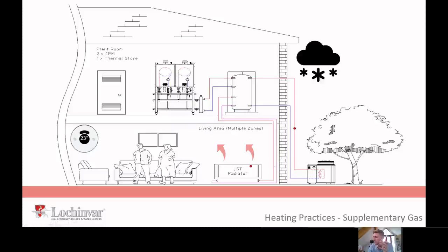So the impact is the kilowatt load goes up to maintain the building at temperature. The heat pump will recognise that the thermal store should be at 50, but it's now 49, it's now 47, it's now 46 degrees centigrade. It's working at 100% rate. We're taking out more energy than we're putting in. So what the boiler does is it turns on. I think this is one of our CPM boilers, so 10-to-1 turn down ratio. It'll put 6 kilowatts in the system to top up to make sure that the user's satisfied, but it won't dominate the load, and that's the key.